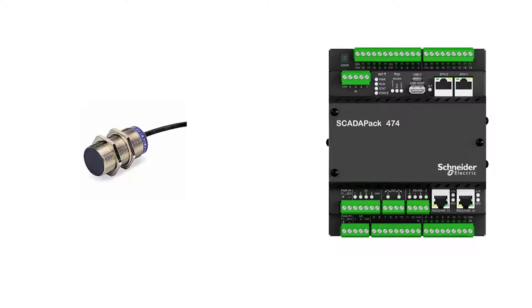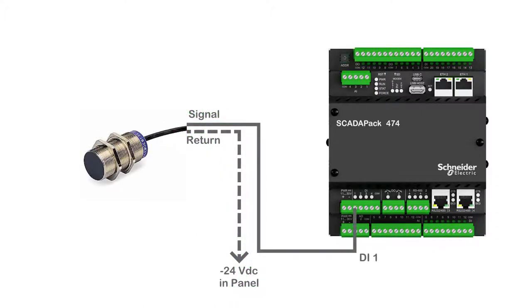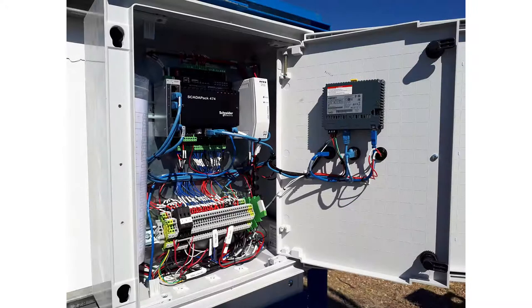Connect the proximity sensor output cable to the following points on the SCADAPack 474: the sensor's 24-volt wire to plus 24 volts in the panel, the sensor's shield to the ground, the sensor's signal wire to digital input 1, and the sensor's return wire to minus 24 volts.